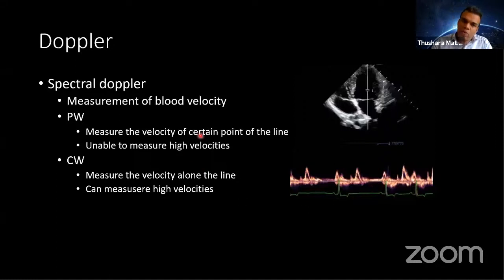Then with continuous wave Doppler, we can measure higher velocities, but there's a disadvantage. We can't apply it to a specific point. It measures the velocity along this line. So it gets the velocity, but along this line. We can't apply any specific point on continuous wave Doppler, but it can measure very high velocities. In mitral regurgitation or aortic valve regurgitation, you get very high velocities, so we can measure those velocities using continuous wave Doppler.